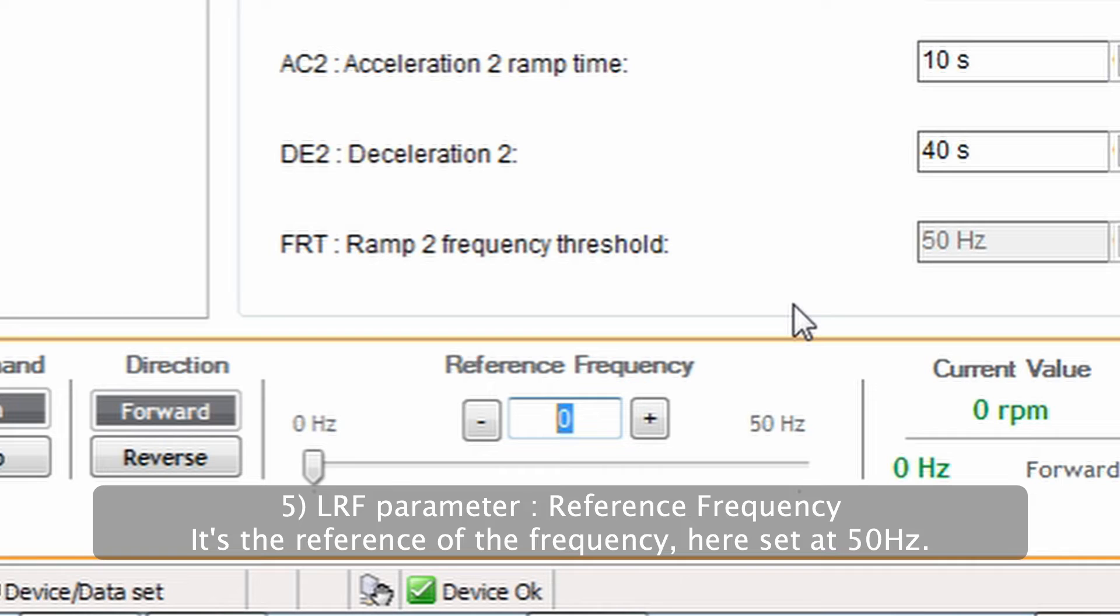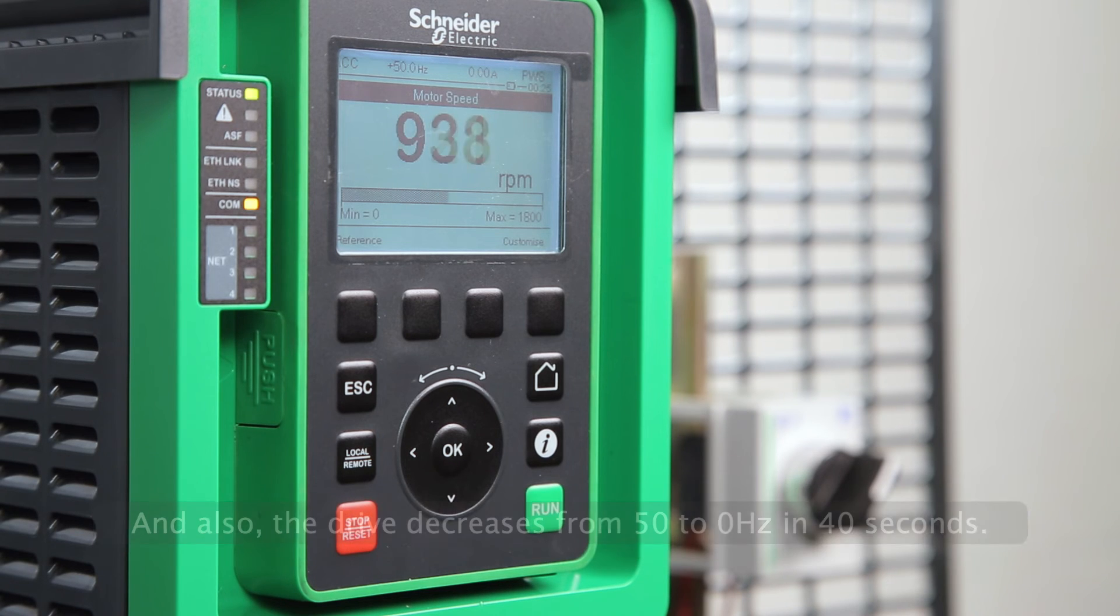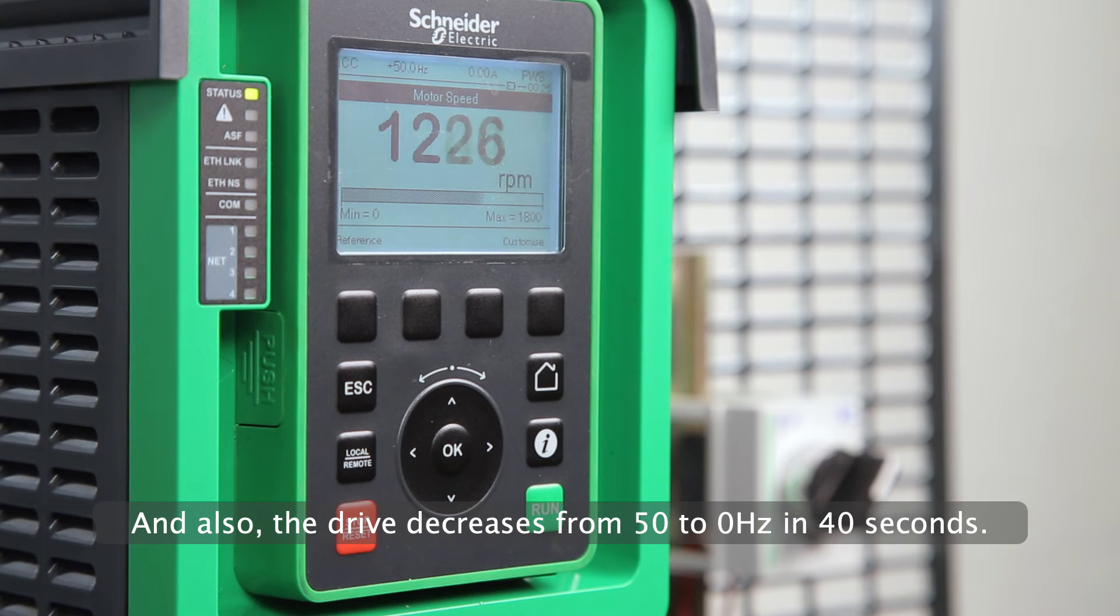LRF parameter, reference frequency. It is the reference of the frequency, here set at 50 hertz. You can see on the graphic display terminal that the drive increases from zero to 50 hertz in 10 seconds. And also, the drive decreases from 50 to zero hertz in 40 seconds.